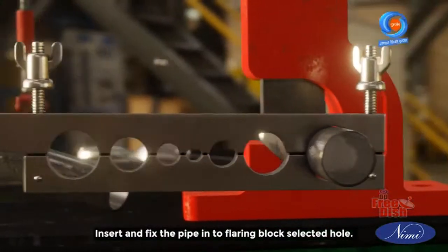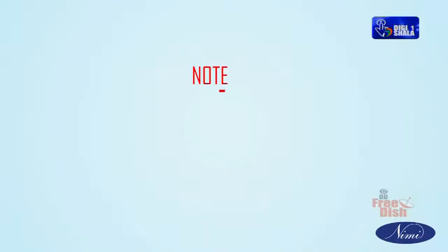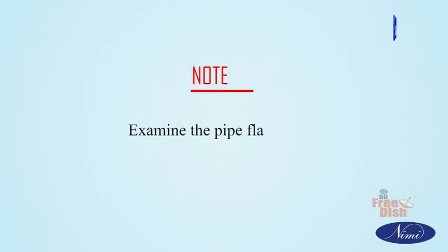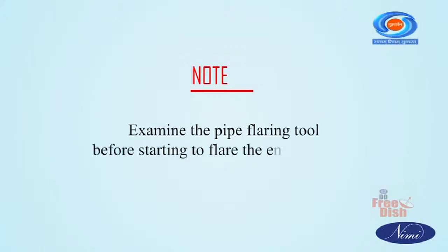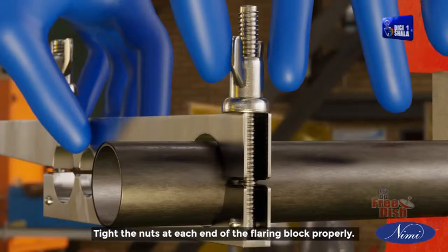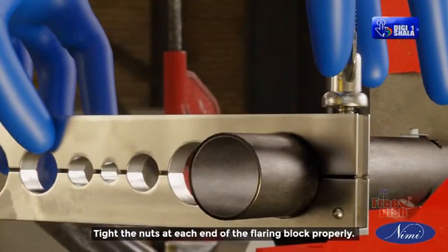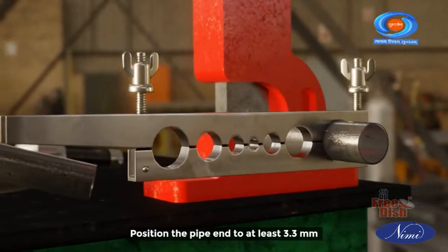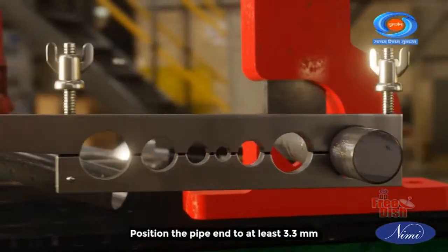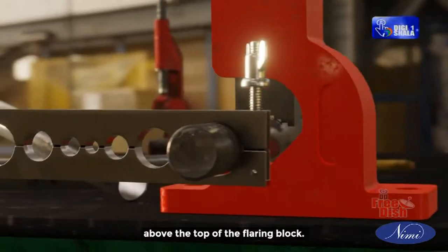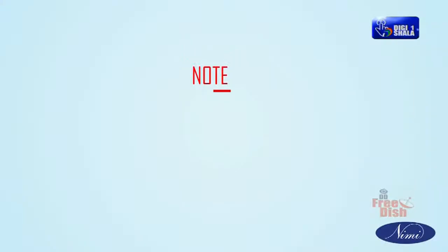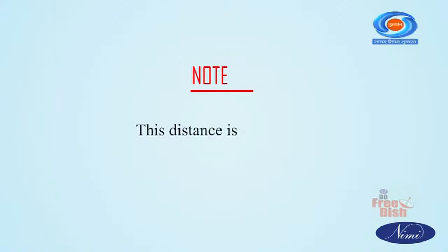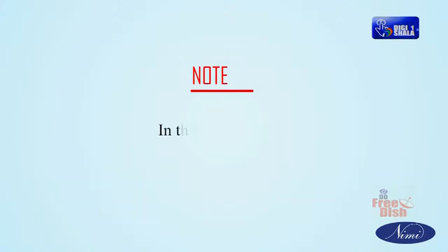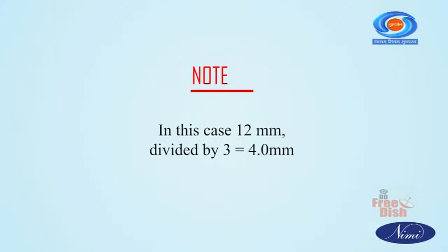Insert and fix the pipe into the flaring block's selected hole. Note: examine the pipe flaring tool before starting to flare the end of a pipe. Tighten the nuts at each end of the flaring block properly. Position the pipe end at least 3.3 mm above the top of the flaring block. Note: this distance is calculated as pipe diameter divided by 3, in this case 12 mm divided by 3 is equal to 4.0 mm.